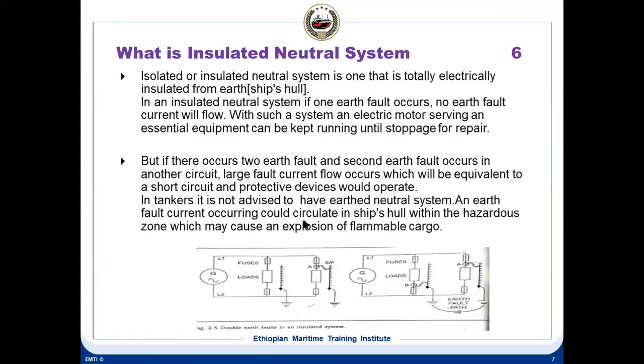The reason why the neutral is insulated is that if you have one earth fault, suppose on the R, Y, B three phases one of the phases gets grounded, the critical machinery will not trip. You will have a leakage current, but it will not trip. But if a second earth fault occurs on another circuit, suppose the Y phase is grounded and the R phase is also grounded, that will be equivalent to a short circuit between the R and Y phases. In that case, the protective device will operate. In tankers, it is not advised to have an earthed neutral system because an earth fault could circulate through the ship's hull within the hazardous zone, which may cause explosion of flammable cargo. So in tankers, we still don't use earthed neutral systems.